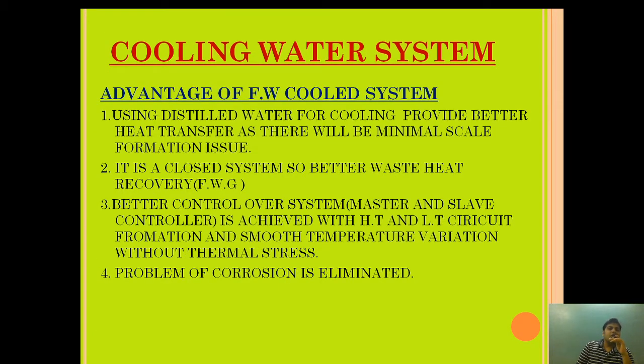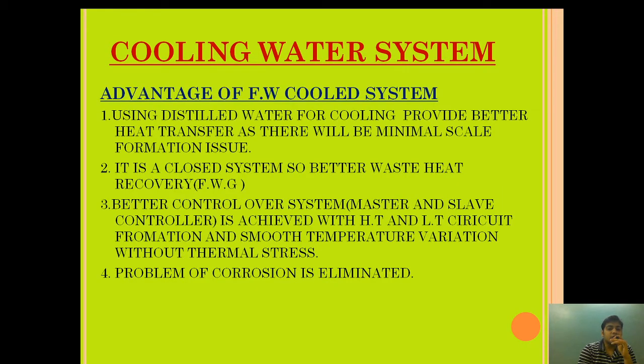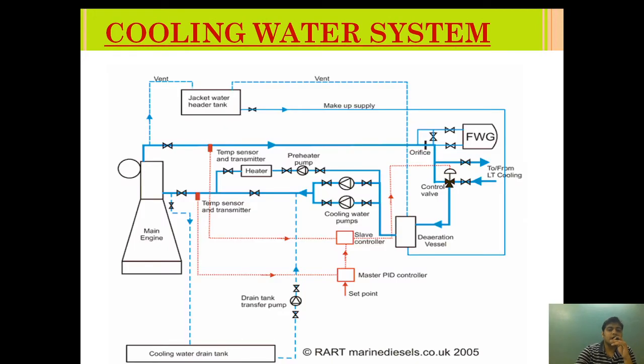The advantages of fresh water cooling: first, using distilled water provides better heat transfer as there will be minimal scale issues. As you can see in the diagram, the whole system is closed and uses distilled fresh water, so minimum scale formation and better heat transfer occur. Also, being a closed system enables better waste heat recovery — the heat gained during jacket cooling is used for fresh water generation.